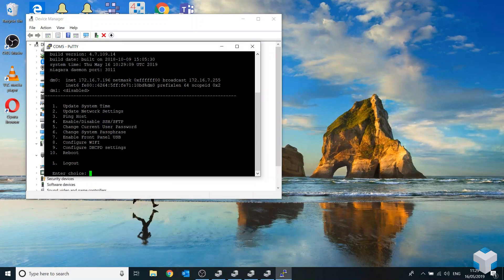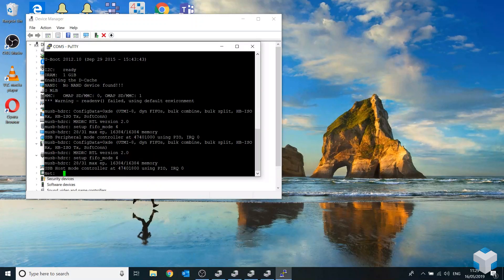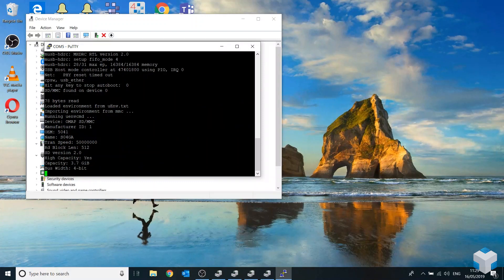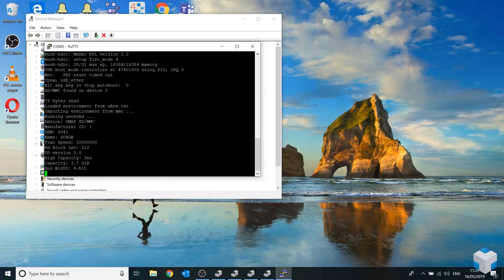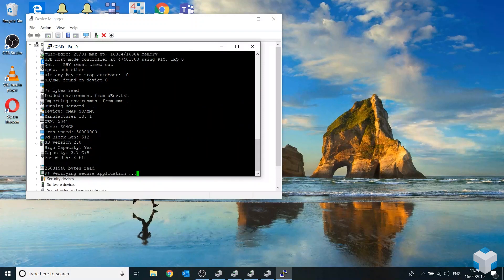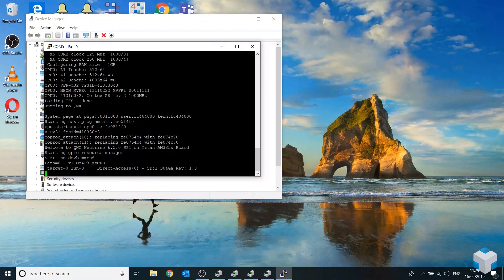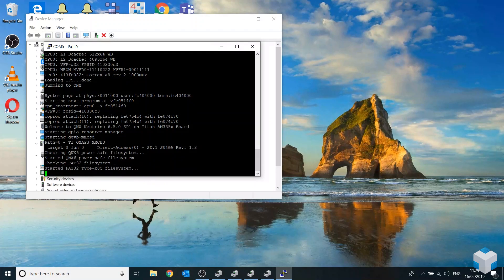Hold down the backup button on the top of the Jace and then power back on the Jace and you'll see the reboot start kicking in. You want to hold this down for about 15 to 20 seconds until it realizes that it wants to do a factory reboot and it will come up on PuTTY.